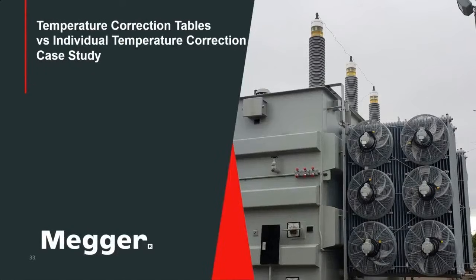And now we will start to get into some of the case studies, and first look at temperature correction tables versus individual temperature correction. As I mentioned earlier, when you are testing at 60 hertz power factor, you want to evaluate the results at 20 degrees C. This is because power factor is very temperature dependent. Earlier I said that power factor is not voltage dependent. That is correct, but it is very correct as well to say that power factor is temperature dependent. And if you're testing in the winter time and then you go and test in the summertime, you may see drastically different values of your power factor.